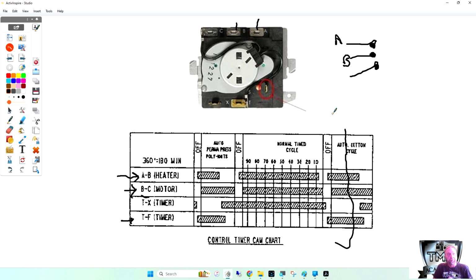That we're looking for 120 volts between A and B? Actually, what I would like you to do is a continuity test or ohms test on the switch. And the reason being is a switch is on line 1 and neutral side, or is it line 1 and line 2? In other words, if I had a light bulb here, this switch would turn the light on and off, right? But where's my neutral? My neutral is here, and my line 1 is here. When the switch is open, neutral backfeeds all the way up to here, and if the switch was open, I'd have 120 volts. Does that make sense? Got any questions there?